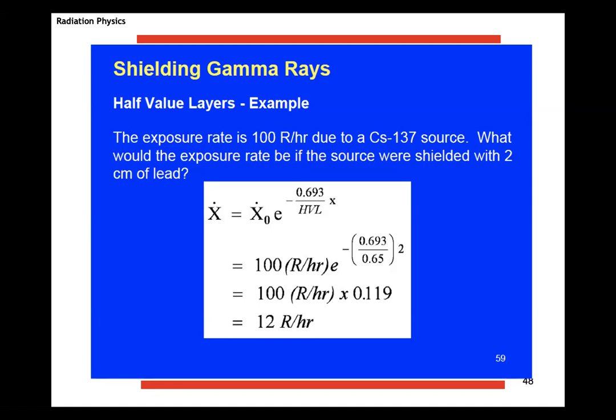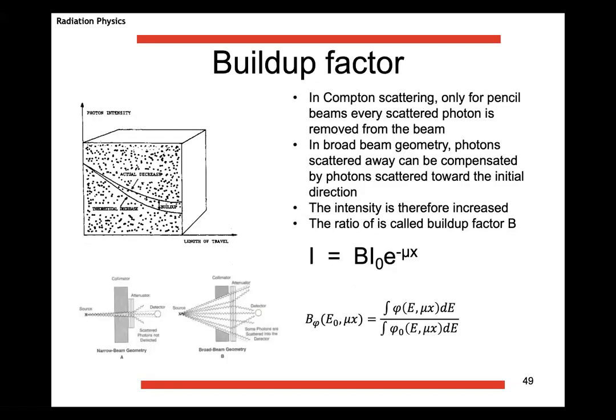That's not enough for radiation protection. Then I have to know how long people stay in that room, because I have to make sure that the Röntgen, or if you prefer the gray, I mean, the total dose is low enough. But that's to show you how easy these calculations are. They're really extremely simple. Unfortunately, though, they are not so simple, because you have a factor which is called the build-up factor.